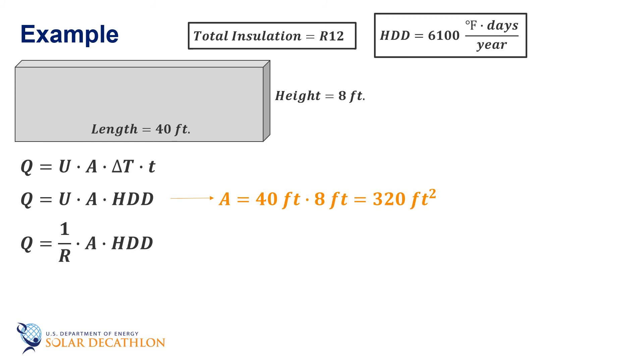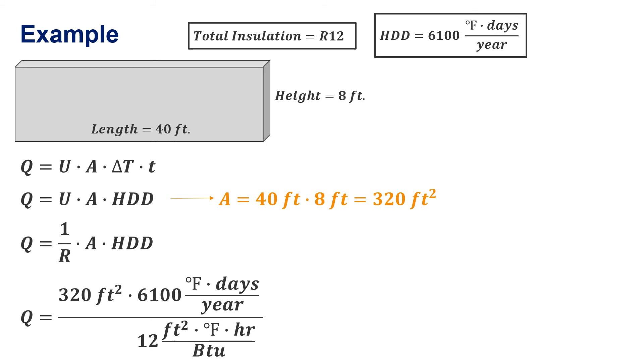Therefore, the heat transfer is 320 square feet times the 6100 degree days. Note the units. Divided by the R value of 12, which also has units, and those units are feet squared degrees Fahrenheit hour over BTU. If you work through the units of each term in this equation, they don't cancel, in particular the time units. So we need to convert days into hours with 24 hours per day in the numerator. With that, the resulting units are BTU, and the answer is 3.9 million BTUs that go through the wall annually.